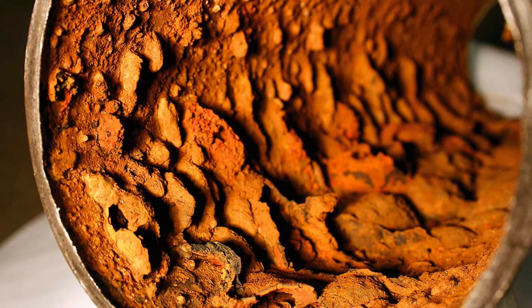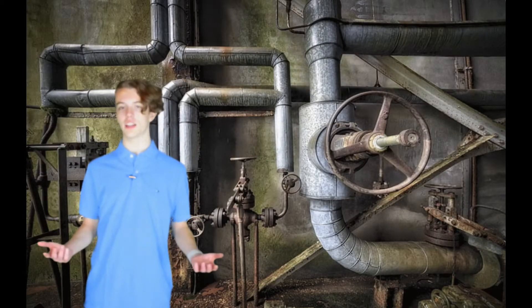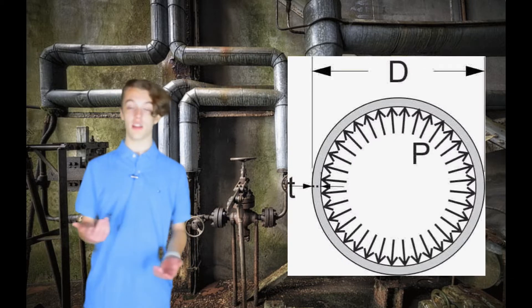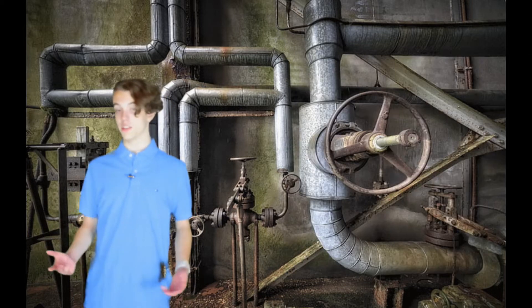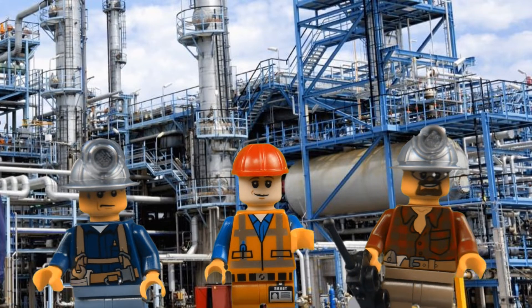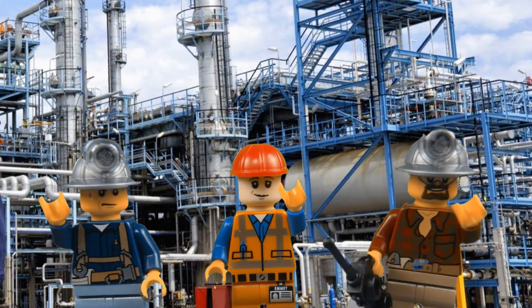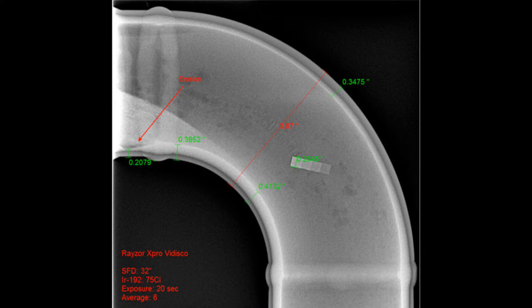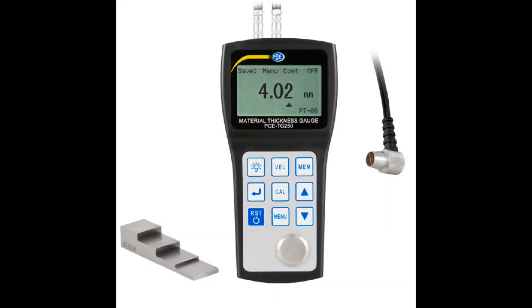The most common way of doing this is to periodically inspect the thickness of the pipe and vessel walls. If they get too thin, they could rupture. So every three years or so they send out crews to manually measure the pipes thickness with x-rays and UT meters.